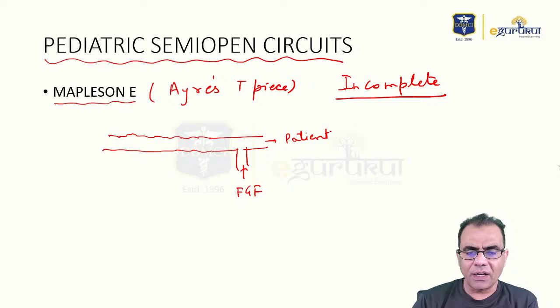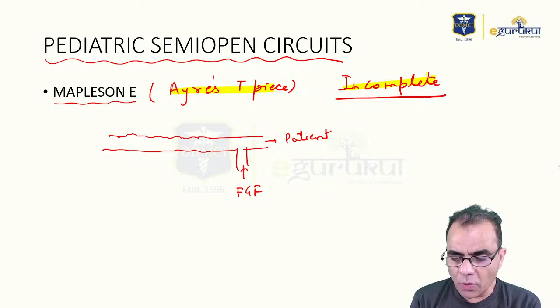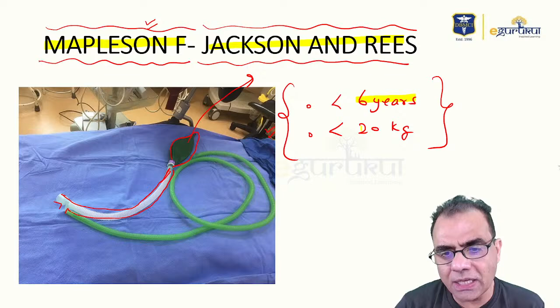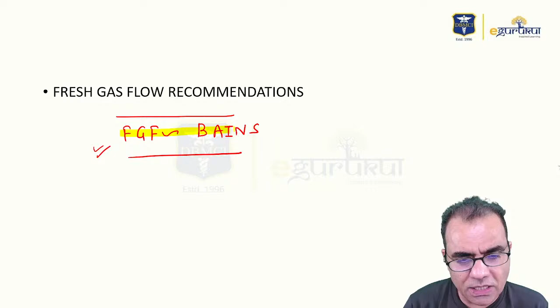Mapleson E is a pediatric circuit, also called Ayre's T-piece, and it was an incomplete circuit. So it was made complete by two scientists, Jackson and Rees, and it is also called Mapleson F. It is the only pediatric semi-open circuit that is used, and it should be used in children less than 6 years or less than 20 kg. And very simply, fresh gas flow recommendations are similar to Bain's.